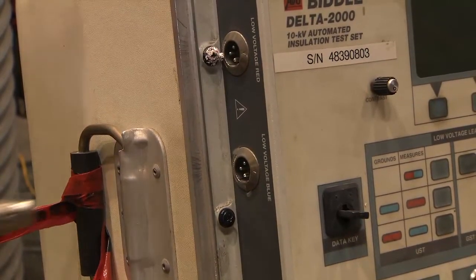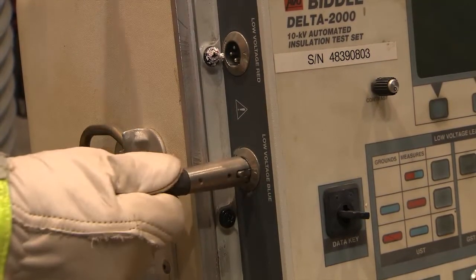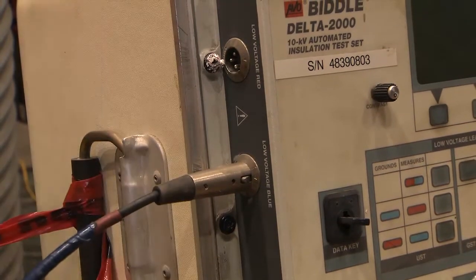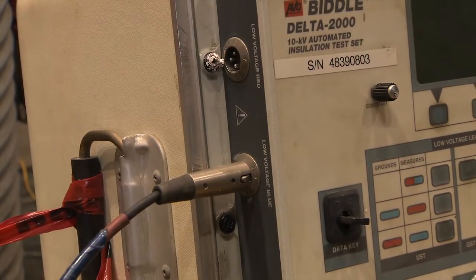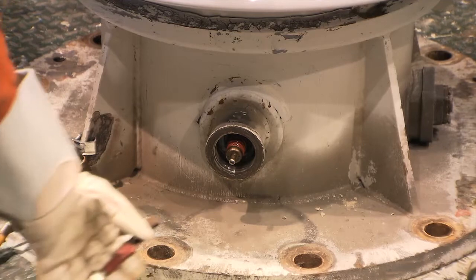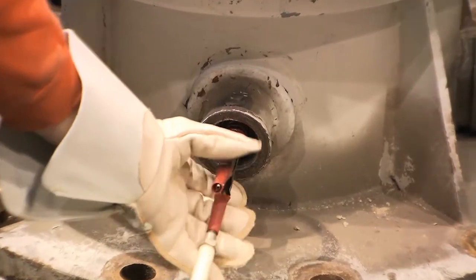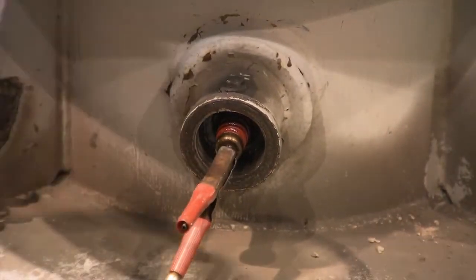Attach one end of the low voltage lead cable to the low voltage blue terminal on the side of the Biddle tester. Attach the other end of the blue low voltage lead cable to the cap tap.